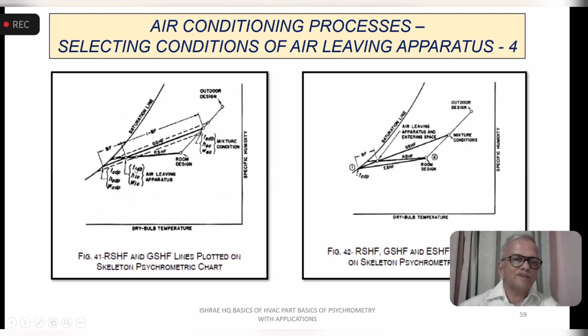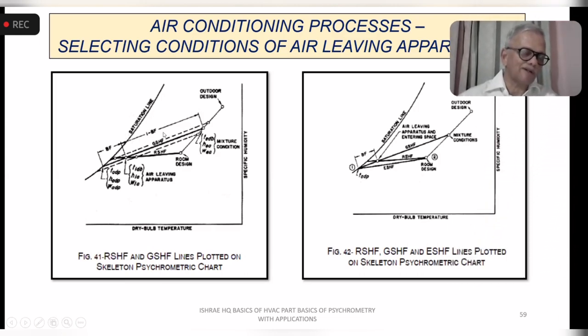The same factors with these values added. So this is bypass factor and this is 1 minus bypass factor. Sometimes this 1 minus bypass factor will be called a contact factor. So it is the efficiency of the coil or the performance of the coil. Ideally, you should reach the saturation line, which we do not reach because of the coil inefficiency. It may go up to 95%, 90% of the coil design, but there is an inefficiency part which is identified and reflected here in the calculation. What it does in effect is that much reduction in the effective value, which means you are enhancing or increasing the amount of air being supplied to the space just to make sure that this coil inefficiency part is taken care of.